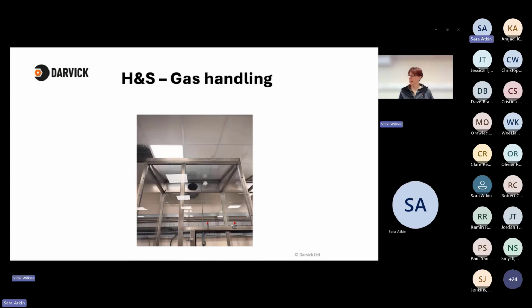There is also another advantage of hydrogen, and that is that if it does happen to escape, it tends to rise. So as you can see here, we've got our safety sensors and we've got our extraction at the top of the machine. It's not going to build up from the ground out. It's not going to flow out underneath all around the lab and accumulate. It will tend to rise, and if you can get it to go out of the building and up, then it's good to go.